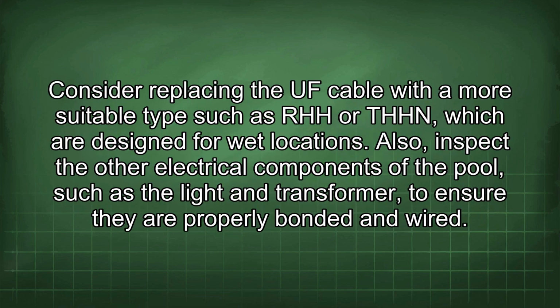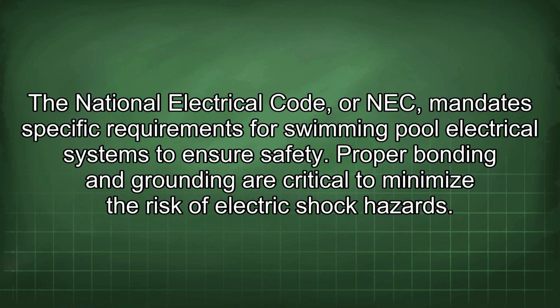Consider replacing the UF cable with a more suitable type such as RHH or THHN, which are designed for wet locations. Also, inspect the other electrical components of the pool, such as the light and transformer, to ensure they are properly bonded and wired. The National Electrical Code, or NEC, mandates specific requirements for swimming pool electrical systems to ensure safety. Proper bonding and grounding are critical to minimize the risk of electric shock hazards.